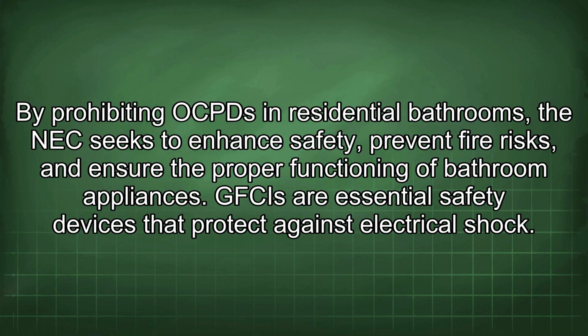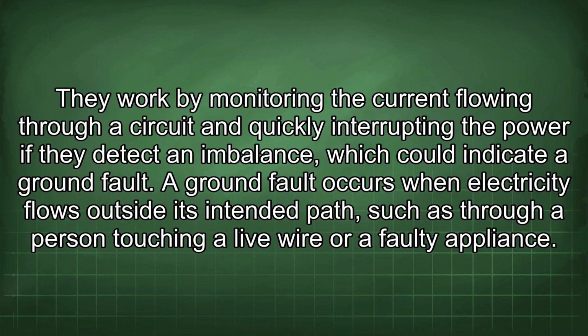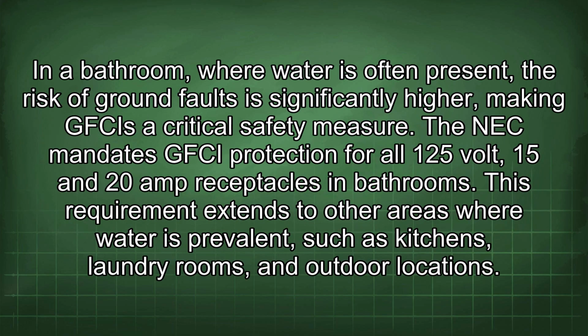of bathroom appliances. GFCIs are essential safety devices that protect against electrical shock. They work by monitoring the current flowing through a circuit and quickly interrupting the power if they detect an imbalance, which could indicate a ground fault. A ground fault occurs when electricity flows outside its intended path, such as through a person touching a live wire or a faulty appliance. In a bathroom, where water is often present, the risk of ground faults is significantly higher, making GFCIs a critical safety measure.